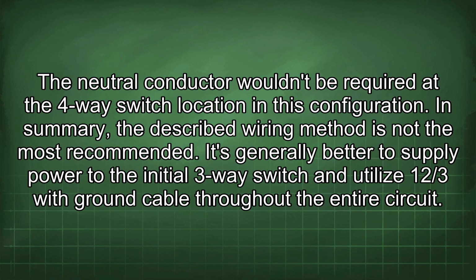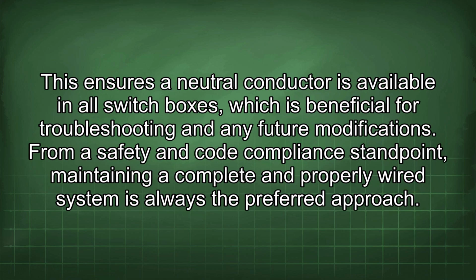In summary, the described wiring method is not the most recommended. It's generally better to supply power to the initial 3-way switch and utilize 12/3 with ground cable throughout the entire circuit. This ensures the neutral conductor is available in all switch boxes, which is beneficial for troubleshooting and any future modifications. From a safety and code compliance standpoint, maintaining a complete and properly wired system is always the preferred approach.